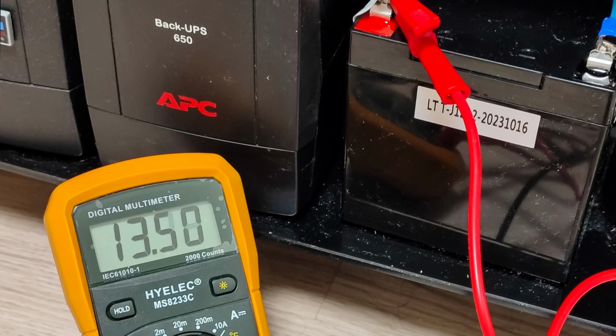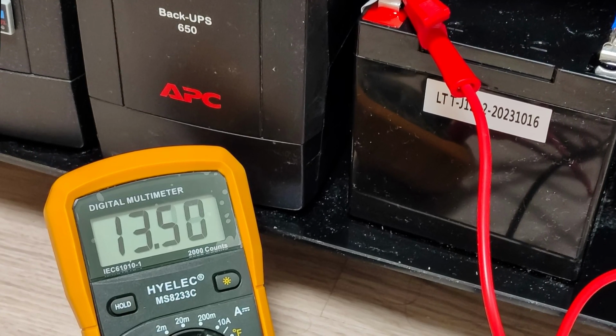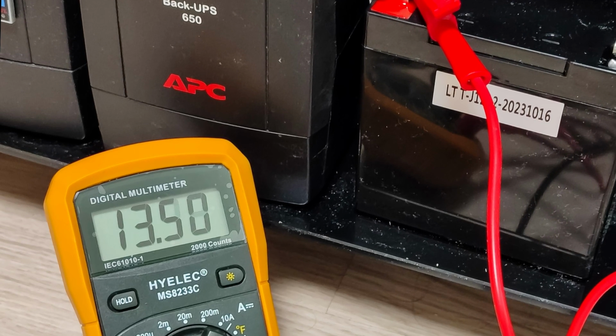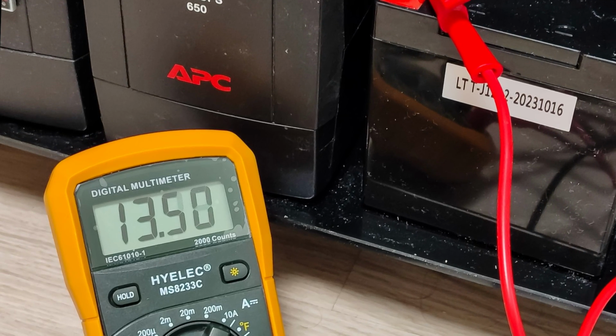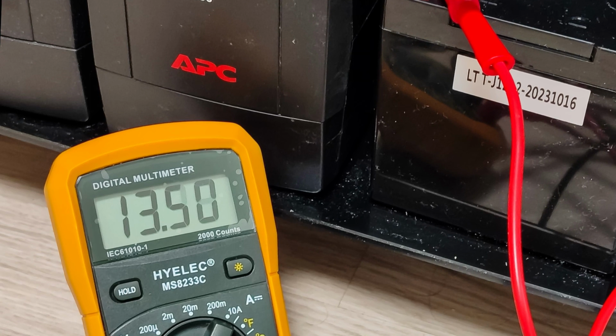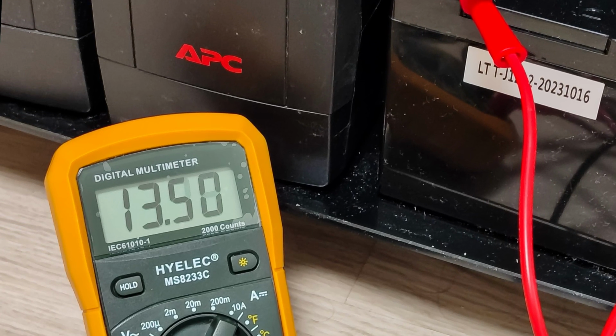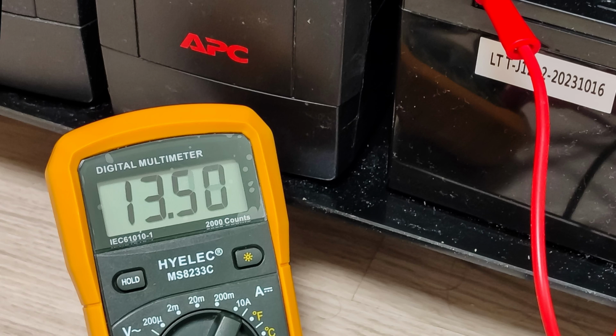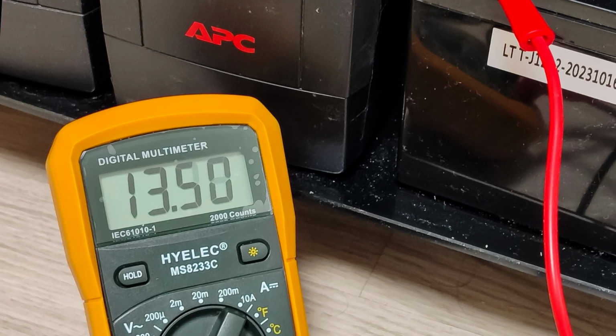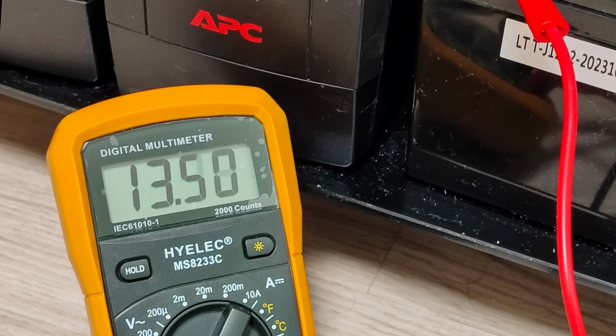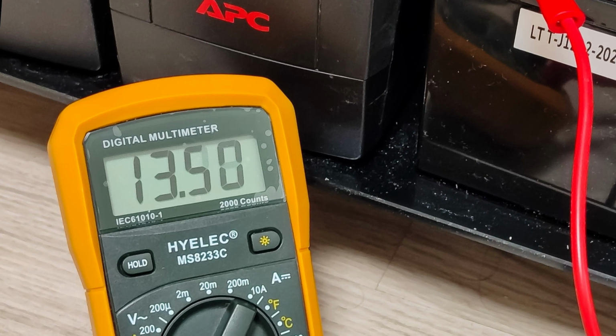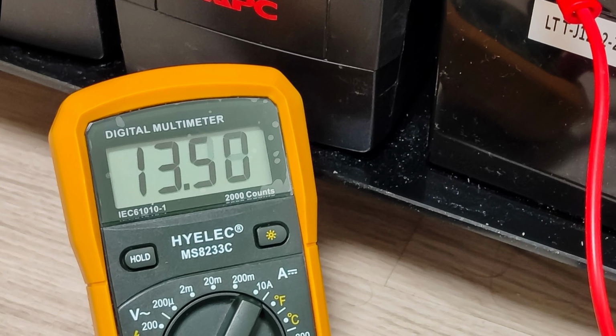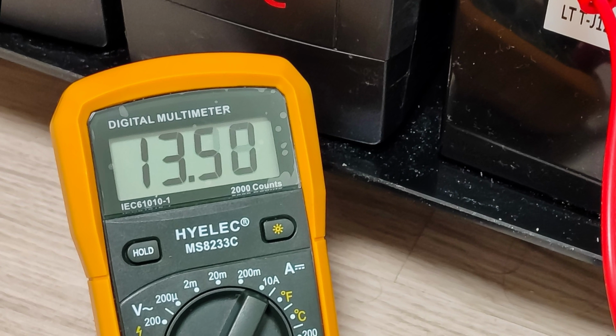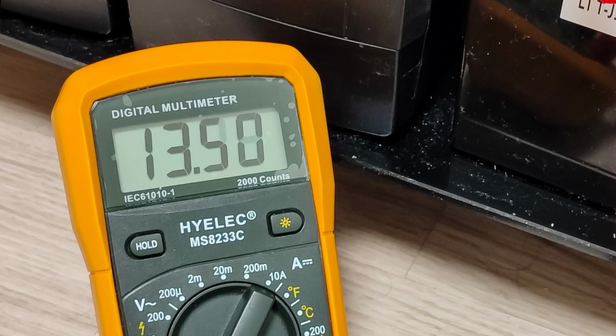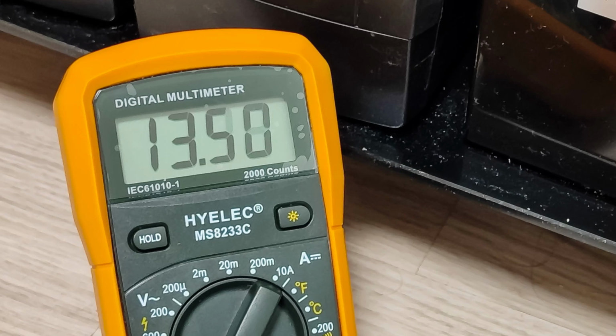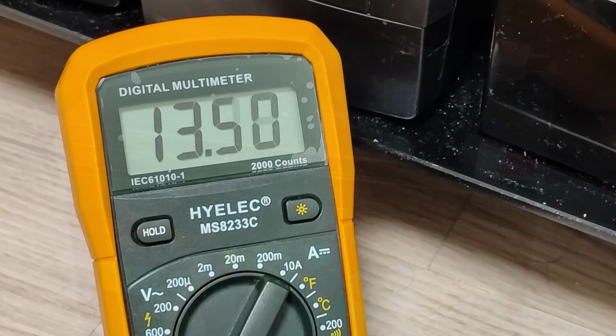This measurement was taken about 18 hours after the battery charging started. By calculations, it should have been fully charged long ago. The voltage is stable at 13.5 volts. Again, I remind you, in uninterruptible power supplies, batteries are in a buffer mode. They are not charged to 100%. For LiFePo4, 3.4 volts per cell is recommended, which is 13.6 volts, and in this case, it's 3.375 volts per cell. It could be a bit higher, but overall, it's within the norm.